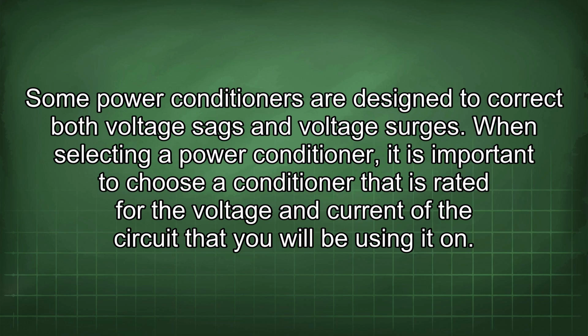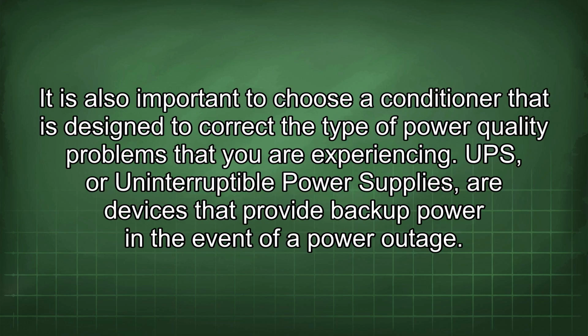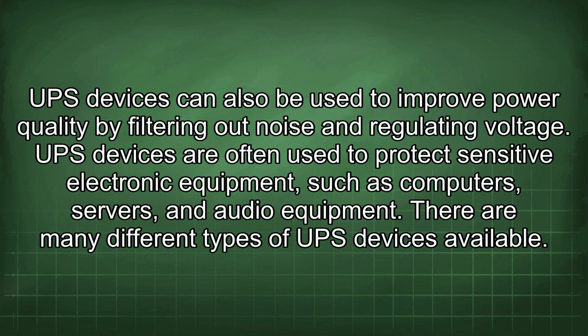When selecting a power conditioner, it is important to choose a conditioner that is rated for the voltage and current of the circuit that you will be using it on. It is also important to choose a conditioner that is designed to correct the type of power quality problems that you are experiencing. UPS, or uninterruptible power supplies, are devices that provide backup power in the event of a power outage. UPS devices can also be used to improve power quality by filtering out noise and regulating voltage. UPS devices are often used to protect sensitive electronic equipment such as computers, servers, and audio equipment.